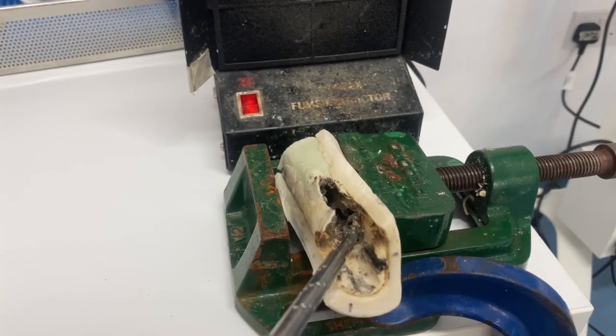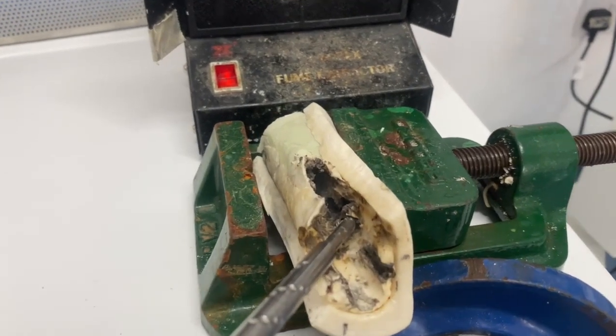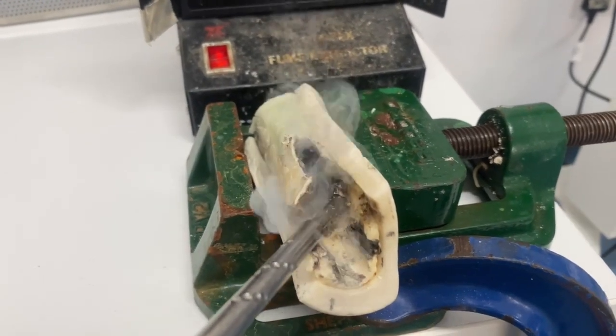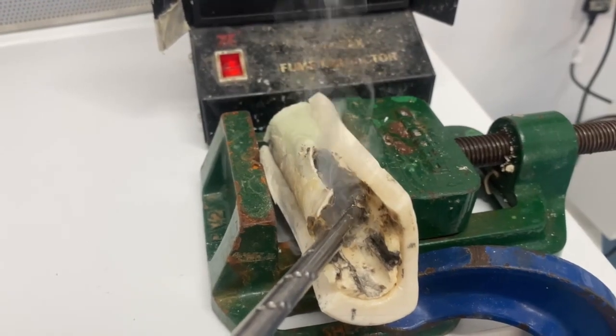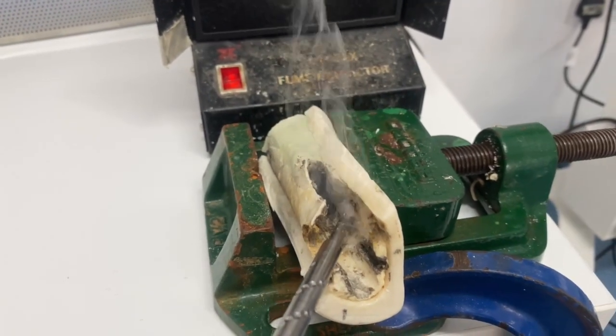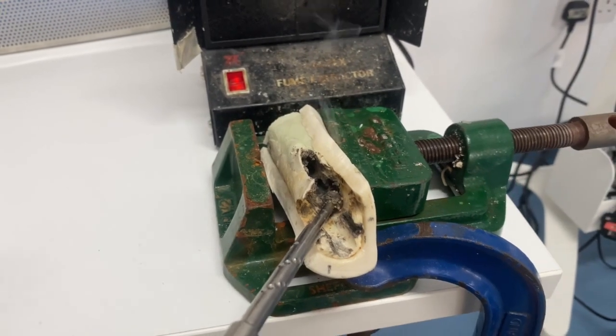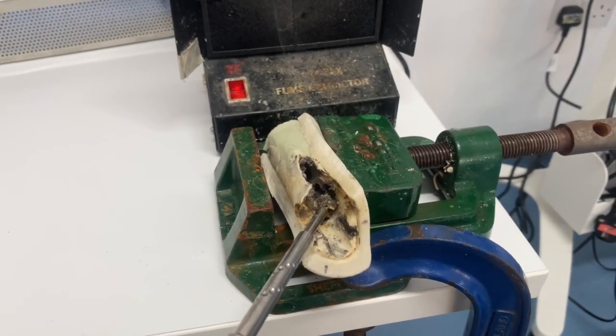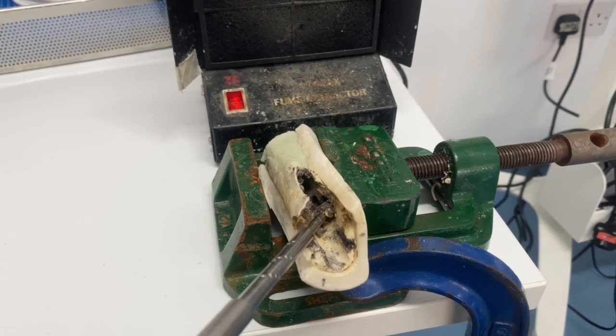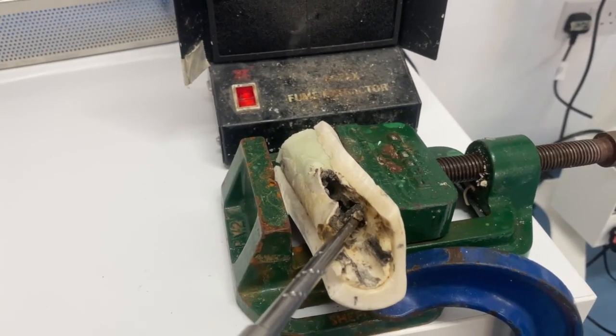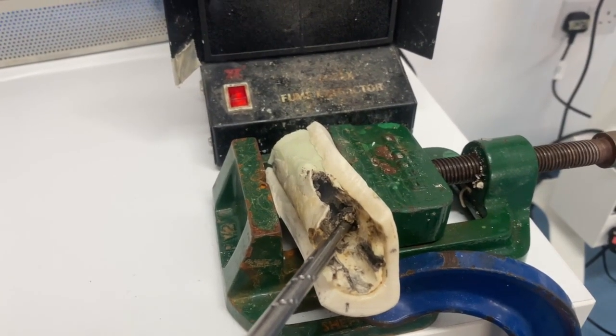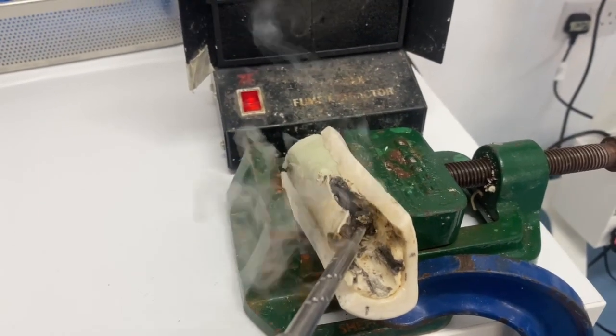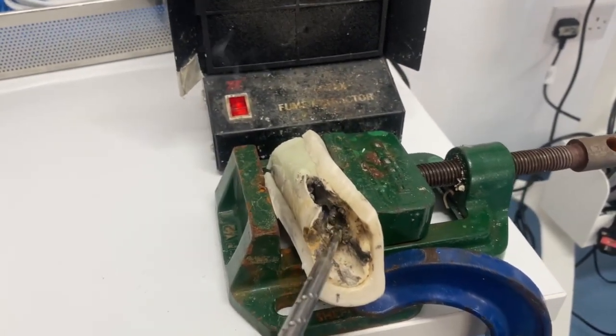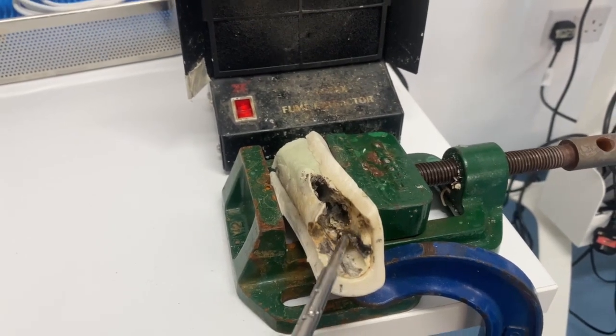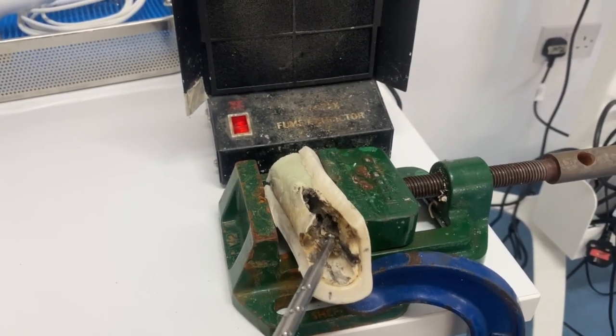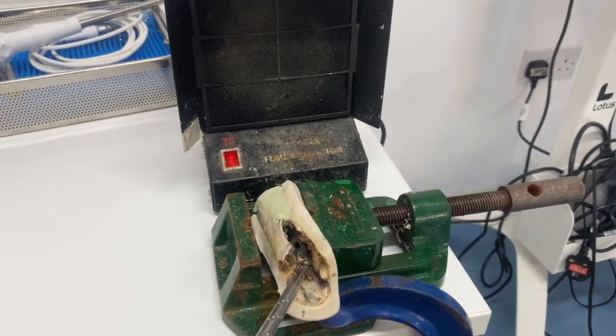So as in all ultrasonic cement removal systems, when the probe touches the bone, the ultrasound is not absorbed by the bone, it's reflected by it because the impedance is very different to cement. And the probe merely rattles and screeches against the bone. That's a very important indication of bone contact, and the surgeon uses that all the time as an indication, and it's important to use that feature.